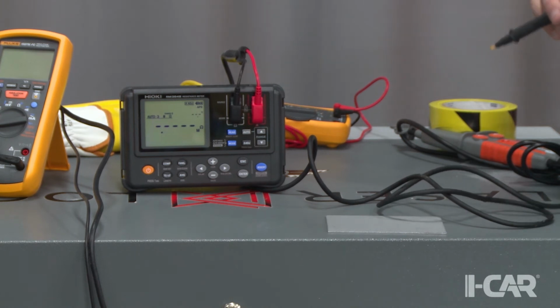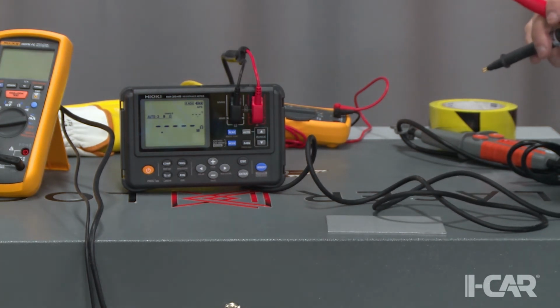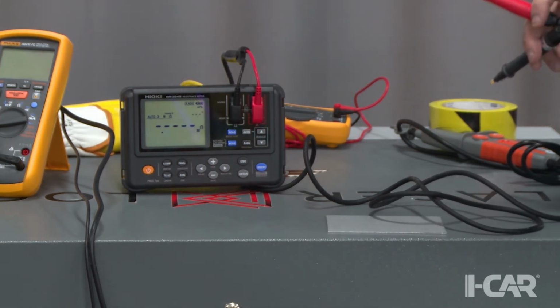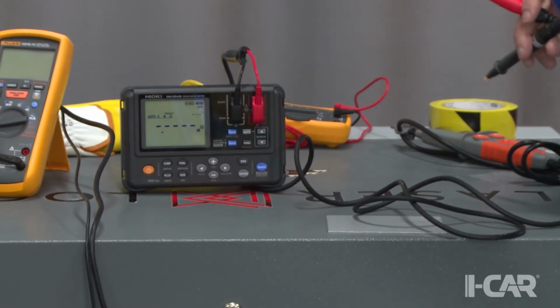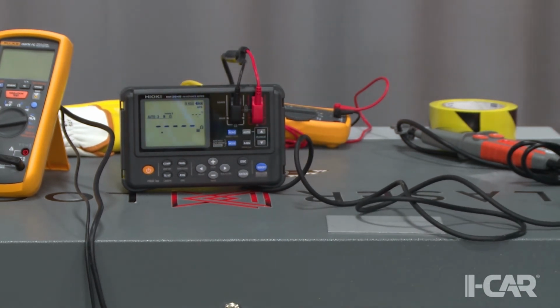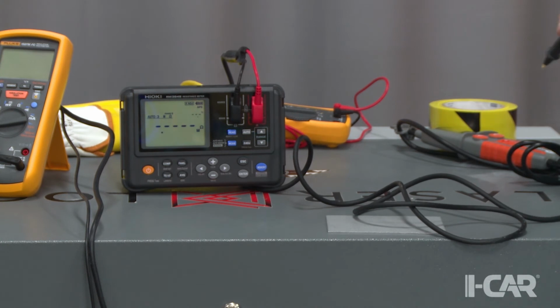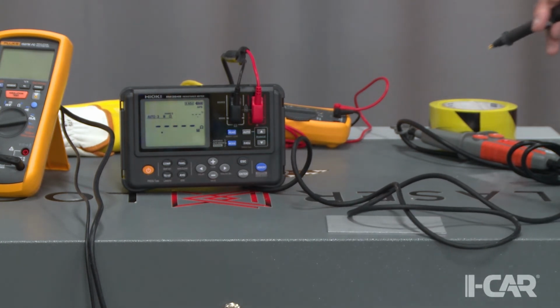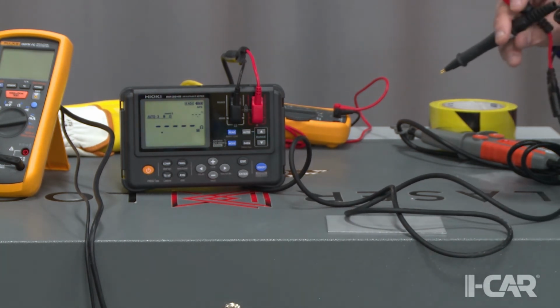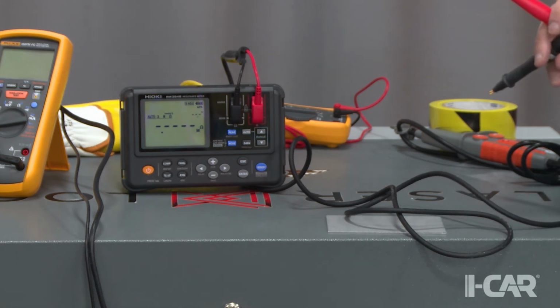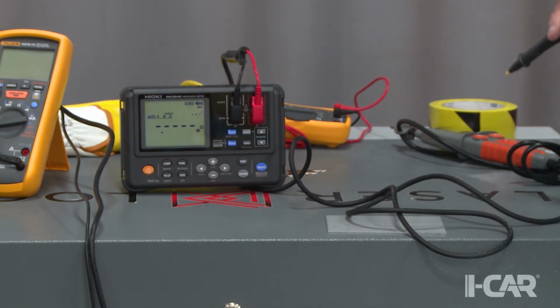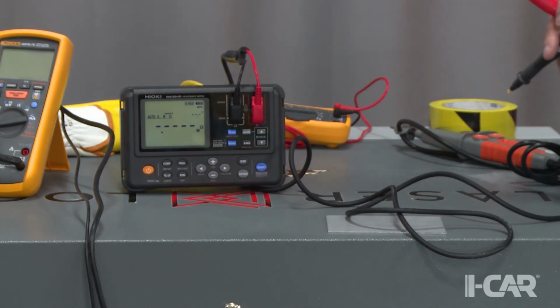And what you do now, you have your cable, now we have a measurement of this cable. Can you tell me how long is this cable? Cable's about 2 feet long overall. Okay, that's like maybe 80 centimeters. I'm a metric guy, 3 feet is approximately a meter. So when I measure from one point to the other, I would expect a measurement of about 0.8 milliohm, a little bit below 1 milliohm.